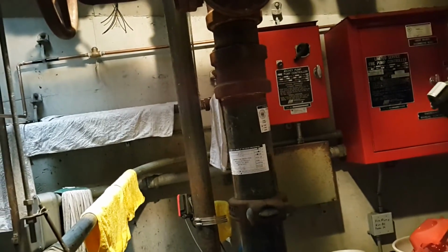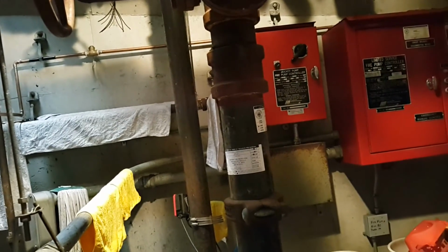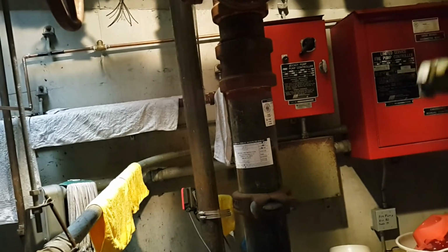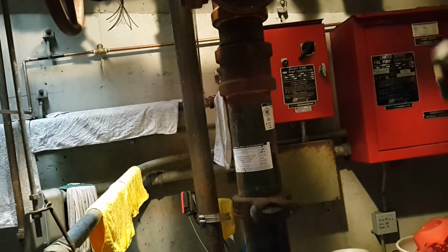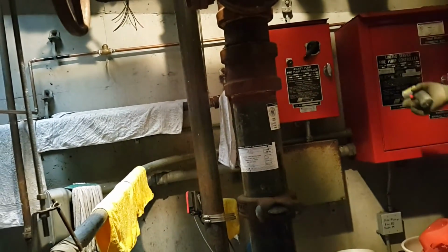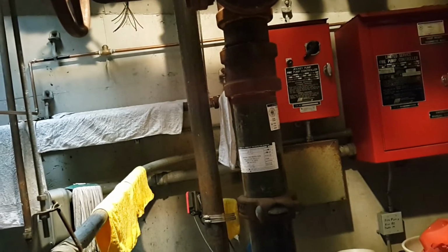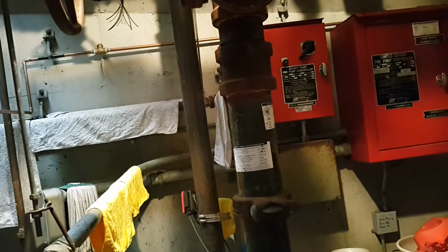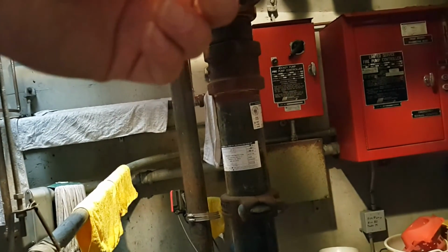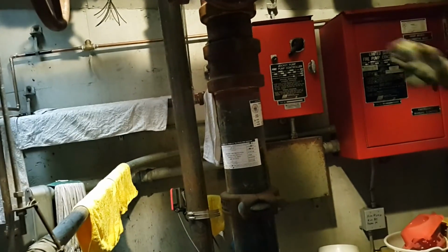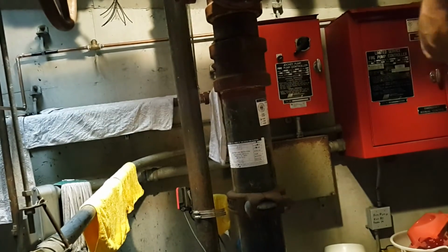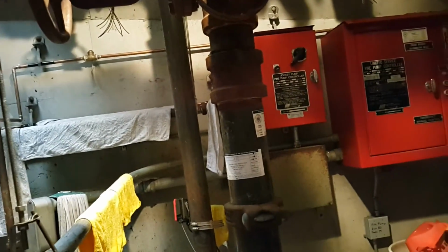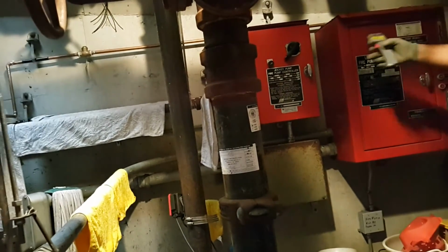If they want it stricter, they make it stricter. California code says you have a 10-minute run timer on there. So if it does kick on for whatever reason and it's not a real emergency, in 10 minutes it's going to shut off and restore everything back to normal. The City of San Francisco wants you to come, turn it off manually, and find out why it started. Is that timer legal? Right now they haven't sent you a letter, so you are still legal. Once you get the letter from the city, you have to remove the timer, come over here, and check it out.